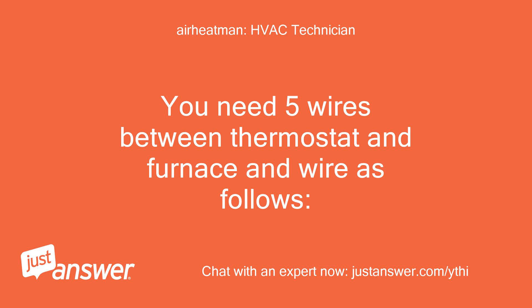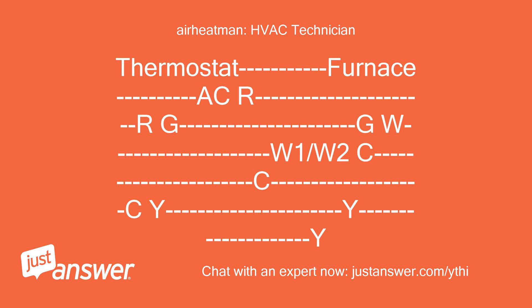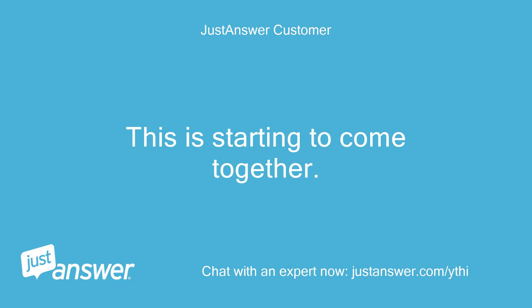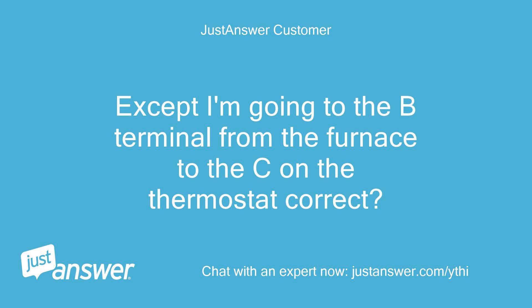You need 5 wires between thermostat and furnace, wired as follows — Thermostat to Furnace: R to R, G to G, W to W1/W2, C to C, Y to Y. This is starting to come together. Except I'm going from the B terminal on the furnace to the C on the thermostat — correct?